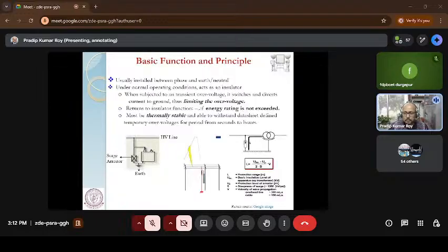So if I talk about the major function of the surge arrestor: in normal operating condition, the surge arrestor acts as a pure insulator, so no current is flowing through it. And when the surge comes, immediately, there should not be any kind of delay, it should convert into a conductor, and all the current passes through the surge arrestor to the ground, and it will protect the devices.